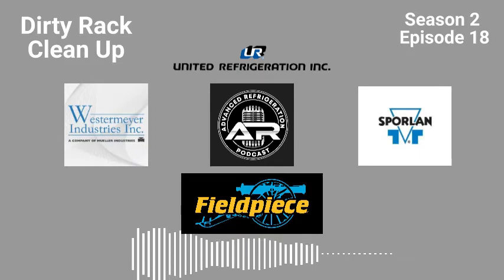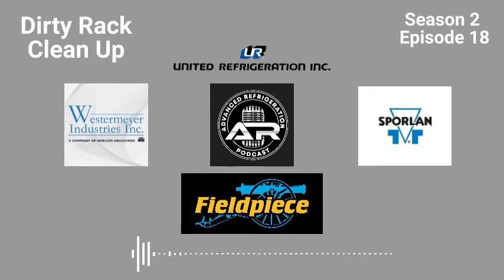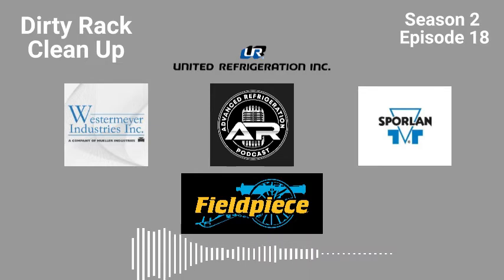Same thing with the rack being dirty. Everything's plugging up in the field. Yeah, it's getting taken out there by the hot gas defrost, but why is it in the rack to begin with? That's where you need to think from. You need to get that rack cleaned up and running properly before you can make this problem go away. You can't just change the filters and expect the problem to go away. We change all the filters. Why is the rack dirty in the first place?